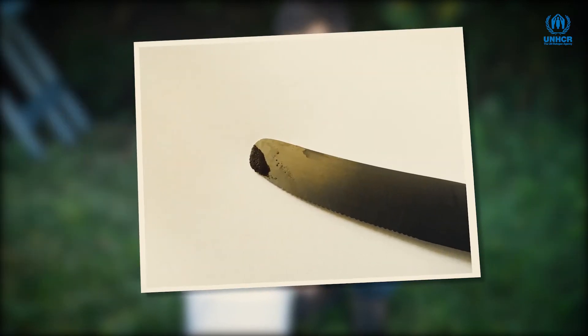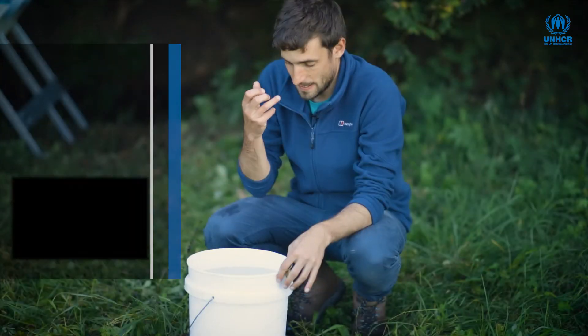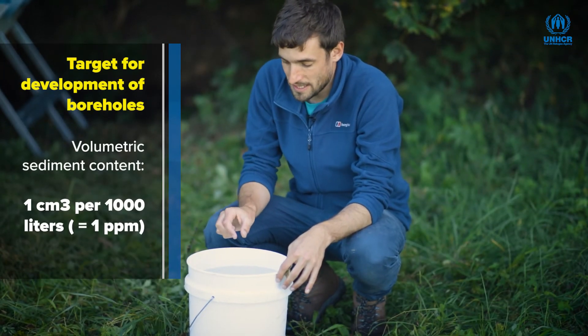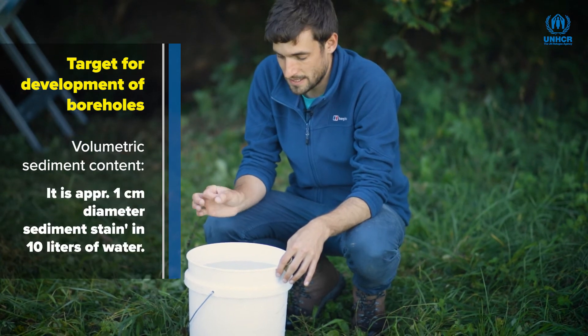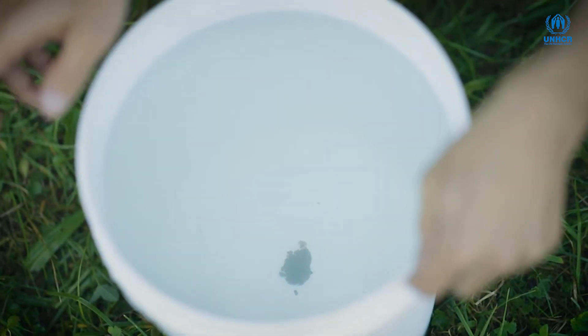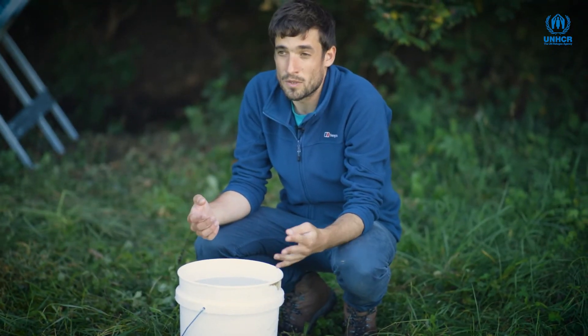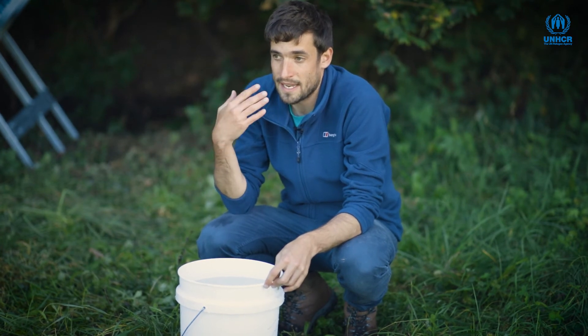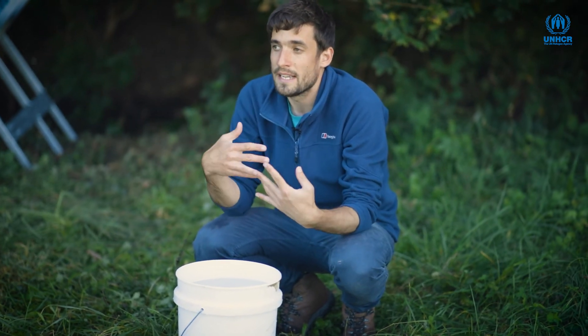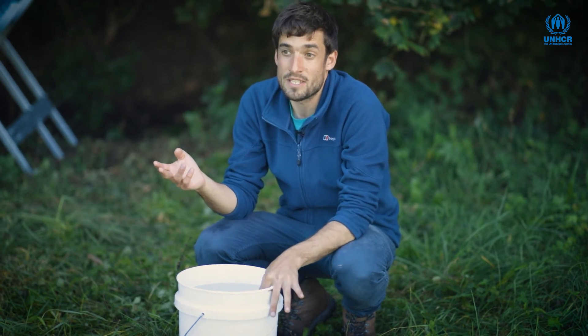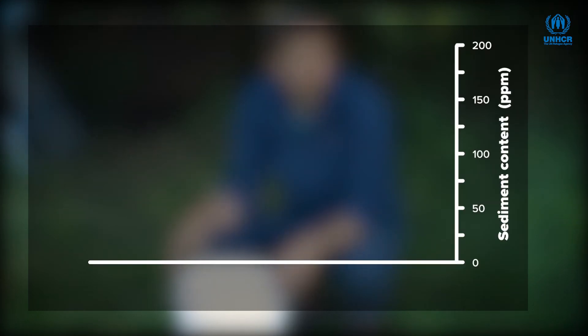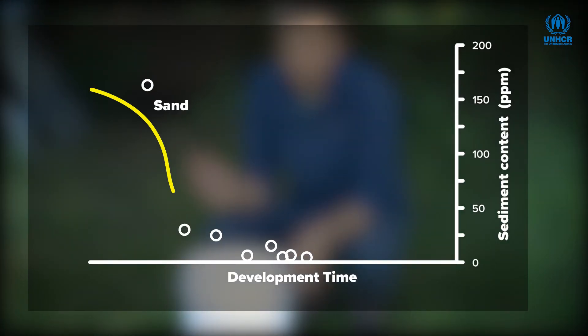We are looking for less than one centimetre cubed in one metre cubed of water, which corresponds approximately to a knife tip of sediment in a 10-litre bucket. What we have here is a circle of sediment in the bottom of the bucket that's about two or three centimetres in diameter. That's indicating that we have too much sediment in the water, which could potentially cause problems with pumping equipment — pipes will be exposed to increased abrasion, which could lead to premature breakdown of the pumping equipment. Carry out one measurement every 15 minutes during development and plot the results against development time.